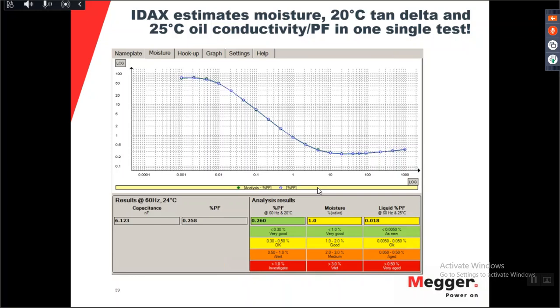Every standard check, I would typically do just one tan delta measurement, maybe over a smaller frequency range, because you can get a quite good indication if something is happening already with a narrow band DFR. But for the full DFR, I would typically do it every 5 years, though there are no recommendations for this. Again, the technical brochure 445 describes different types of maintenance processes, if you would do condition-based or time-based tests. So all of this depends on what type of process you have in your maintenance group.